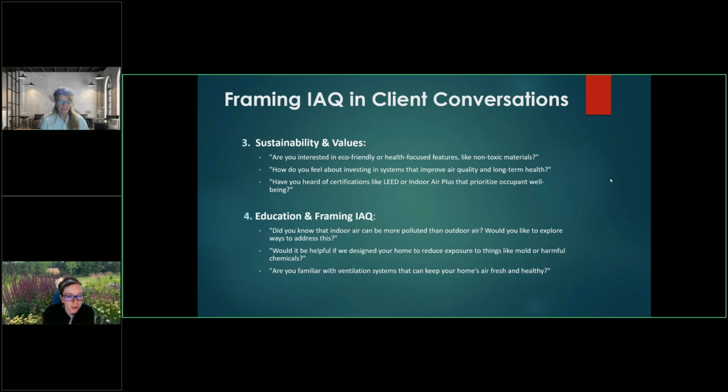Did you know that indoor air can be more polluted than outside air? We're going to talk a little bit about that. I don't know if anybody's seeing the indoor air quality indexes for the areas they live in, especially if you're anywhere near wildfire prone areas. We had a spike on our monitor here. PM 2.5 was high. We thought it was because we were doing demo in our basement. Turns out the outside air quality was actually worse, and our ERV was bringing that into the house.